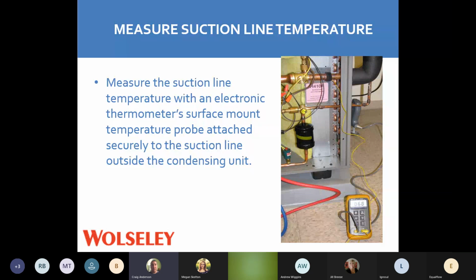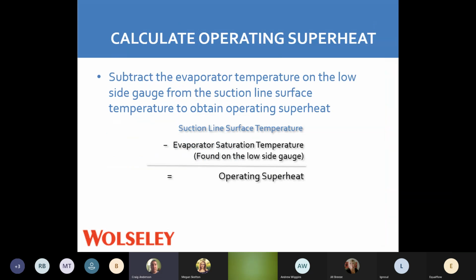So saturation temperature, suction temperature. Once we have these, we have our suction line temperature and we have our evaporator saturation temperature that's found on the low side of our gauges. Once we have that, we subtract it. That's going to tell us our superheat. Pretty simple. Measure the temperature of your pipe outside, find your saturation temperature on your low side gauges. That's going to tell us our superheat.